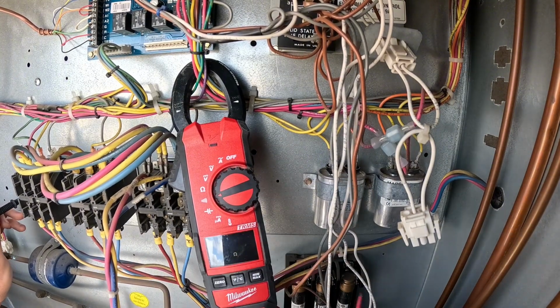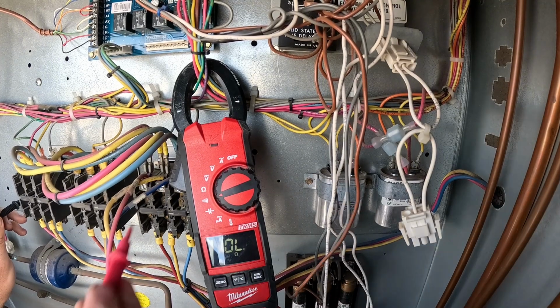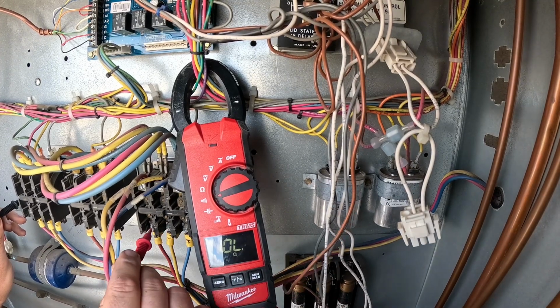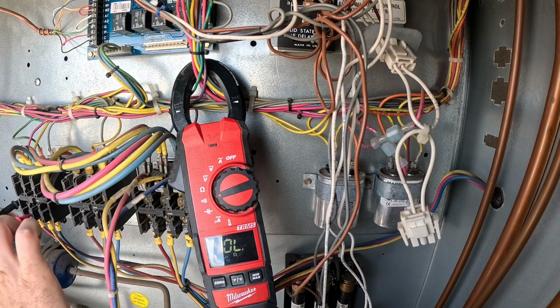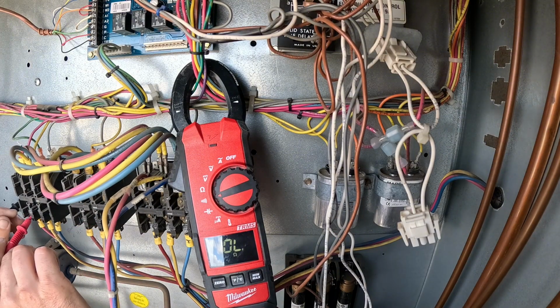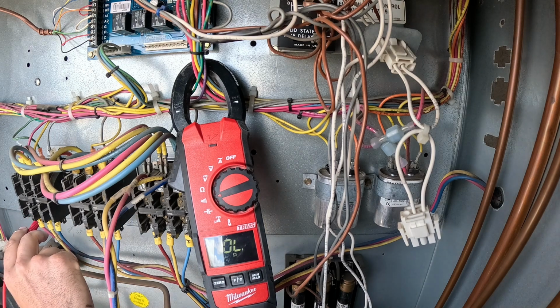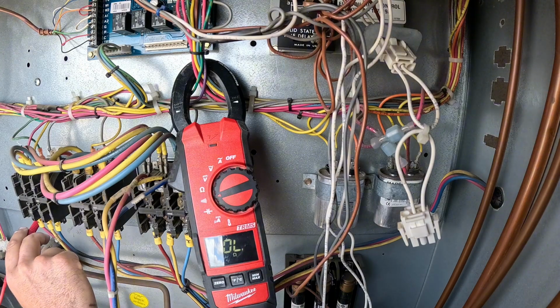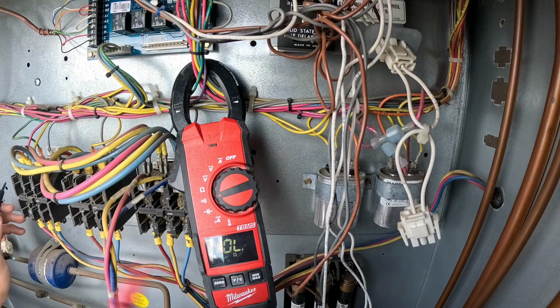I can tone as well, but when I check components, I want to check resistance through my ohm reading. Okay, so we have nothing to ground. Maybe my condenser fan motors. That's my contactor, my low voltage side that's connected to ground, so that's why it was beeping. Okay, it doesn't look like we have anything obvious going on to ground.